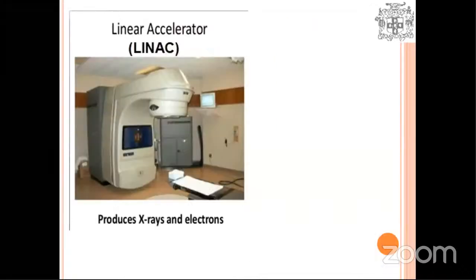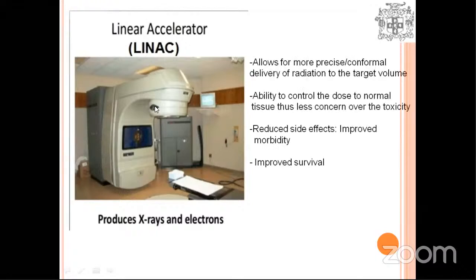As a result, it has given way to its newer cousin, which we call the linear accelerator, capable of producing both X-rays and electrons. The beauty of this machine is that it allows more precise and conformal delivery of radiation to the patient, and the ability to control the dose to normal tissues. As a result, toxicity is less, side effects are less, the morbidity I was telling you about is improved, leading to improved survival.